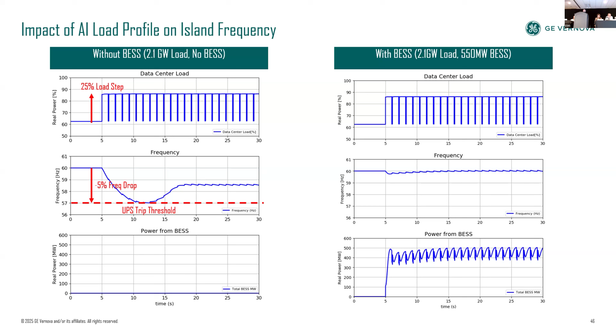Now, energy storage solutions in this particular case have a dual role. One, it is used as a backup to provide relief until the cold reserves are started, which takes anywhere from 20 to 30 minutes or so. So this BESS system is designed to provide a dual purpose. And we can see from the chart on the right, when the BESS system reacts based on the change in the frequency that you see at the terminal, it can compensate for that large load loss so that the generation system is stable and we can contain the frequency within acceptable limits.